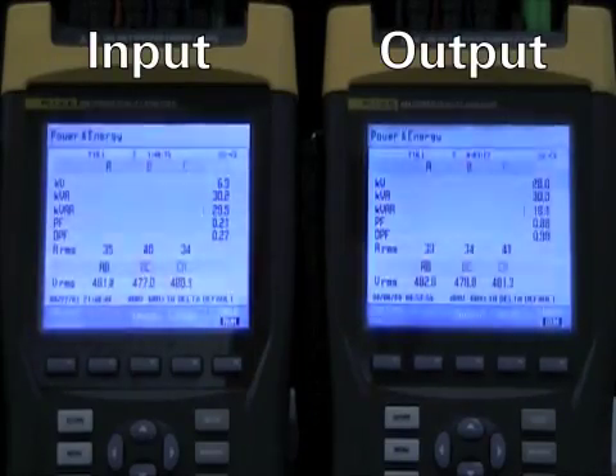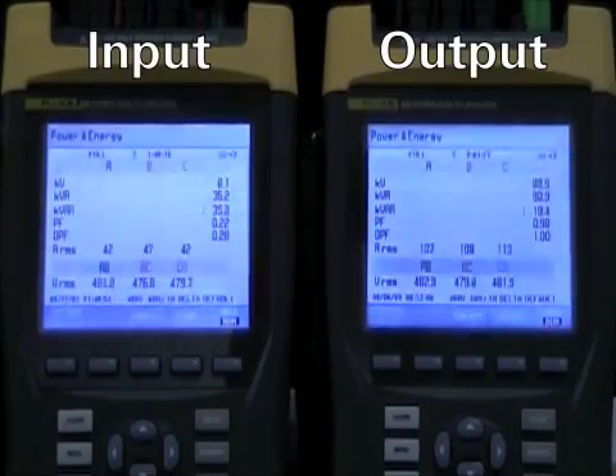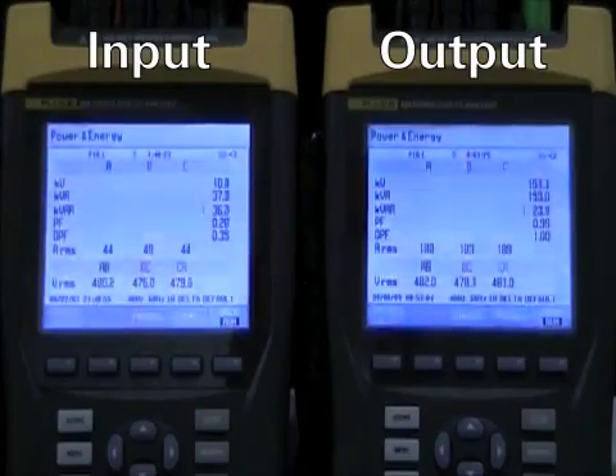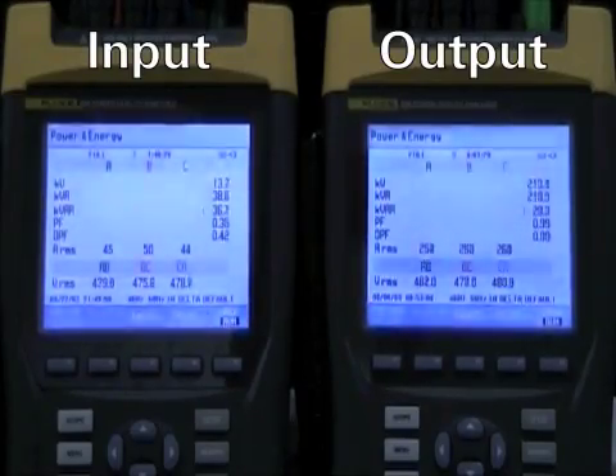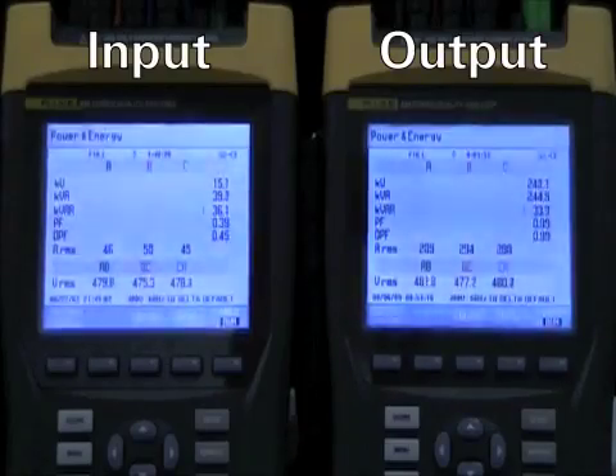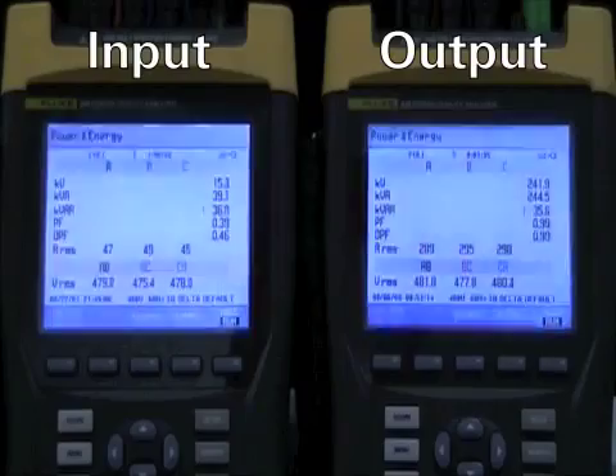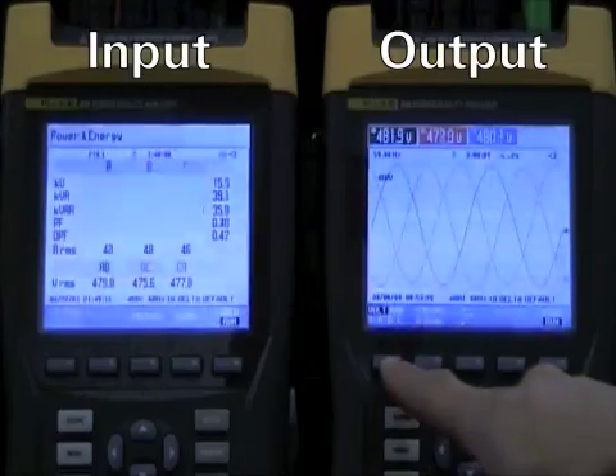If you look at the kilowatt metering on the right, you'll see the output kilowatts begin to rise. 100 kilowatts. 200 kilowatts, eventually stabilizing between 240 and 250 kilowatts of real resistive load. If you look at the kilowatt metering on the left, you see the input of the UPS is drawing only 15 kilowatts from the utility.